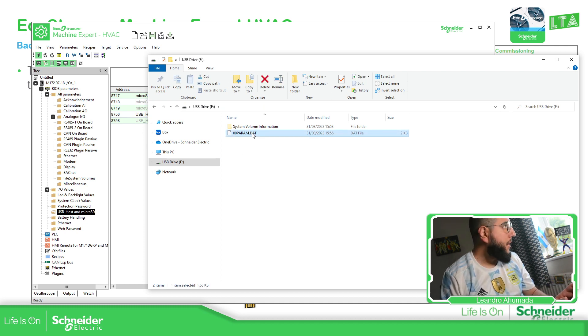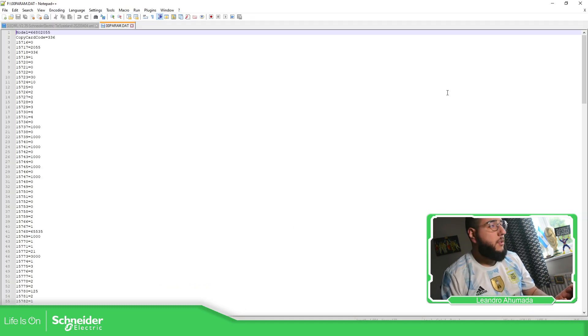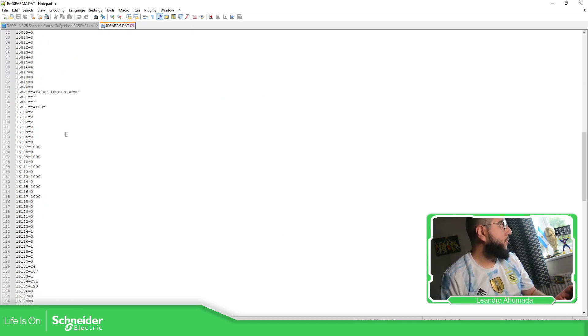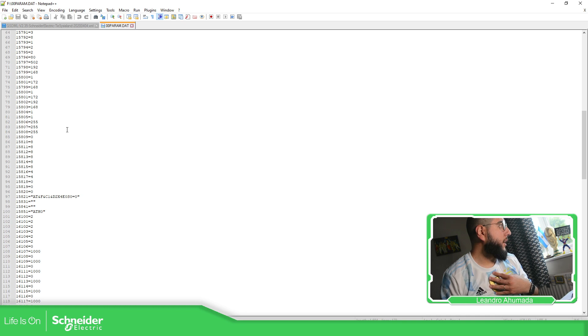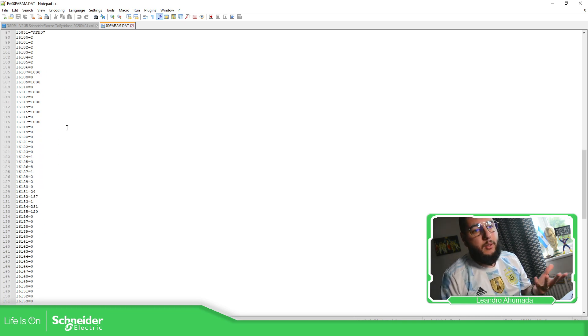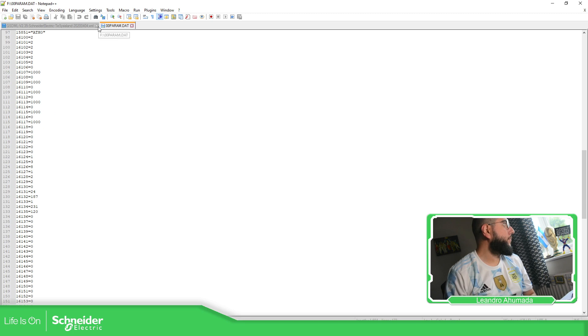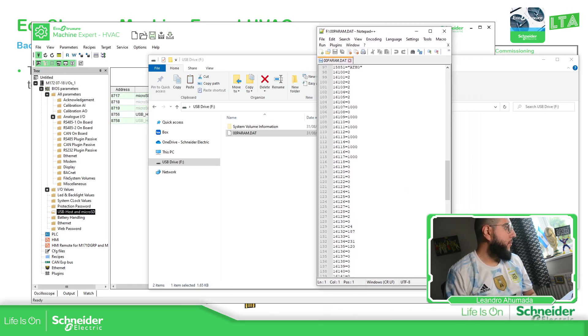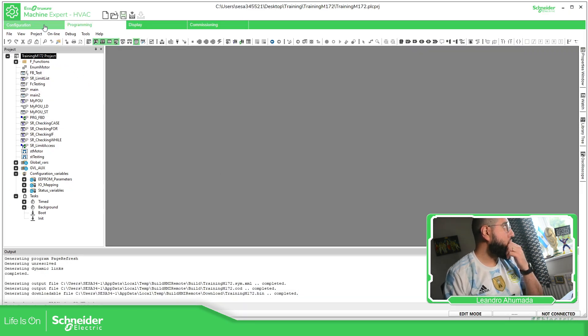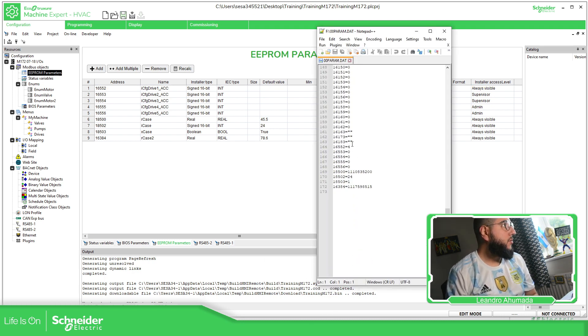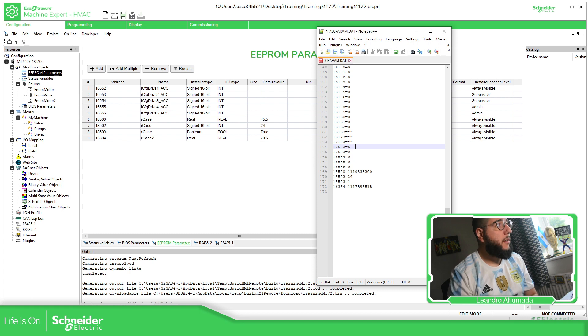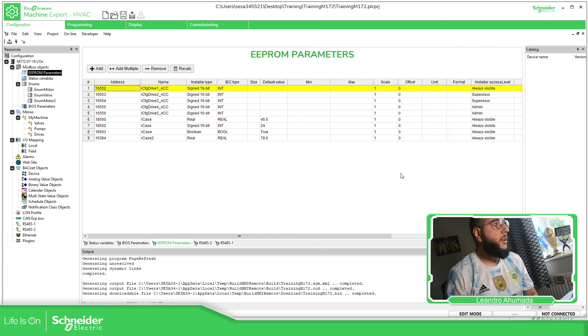Now I put the USB back into the PC. As you can see, I have the parameter file which contains the complete list of variables of the PLC. In my case, I already defined one variable with the number four — that variable with number four is parameter 16452. It has the number four. If I want, I can change this to number five and save it.